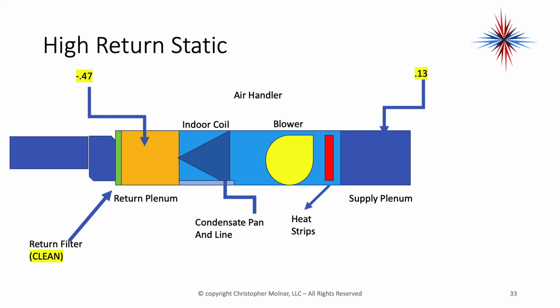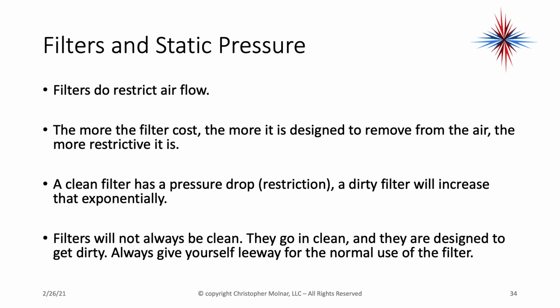Okay, so if I have a clean filter and I still have the same values, we have to realize a couple things on filters. Filters restrict airflow. The more the filter costs, the more it is designed to remove from the air, the more restrictive it is. A clean filter has a pressure drop. A dirty filter will increase that exponentially. Filters will not always be clean. They go in clean and they're designed to get dirty. Always give yourself a little leeway from the normal use of a filter.